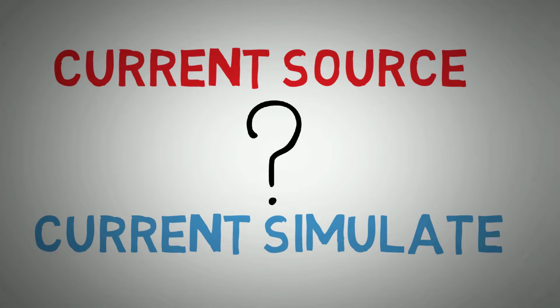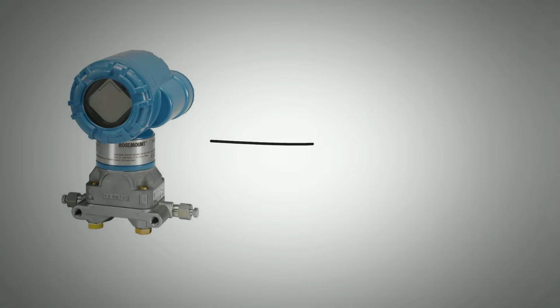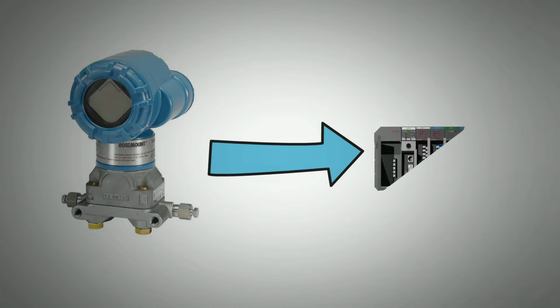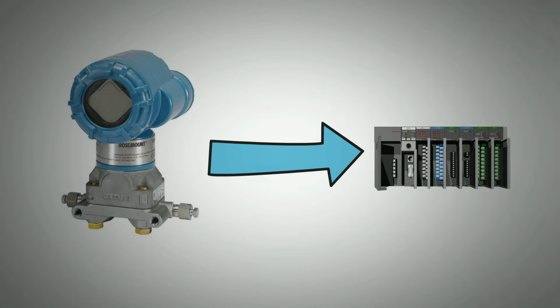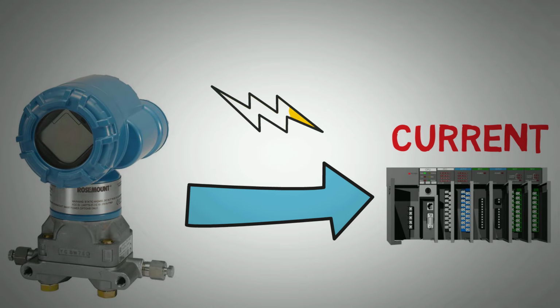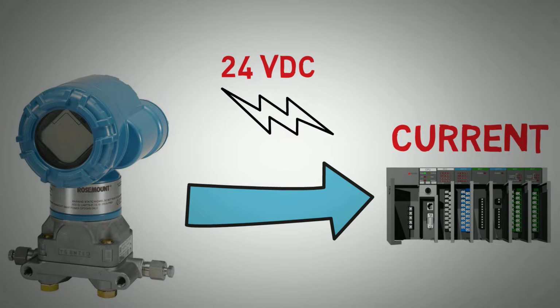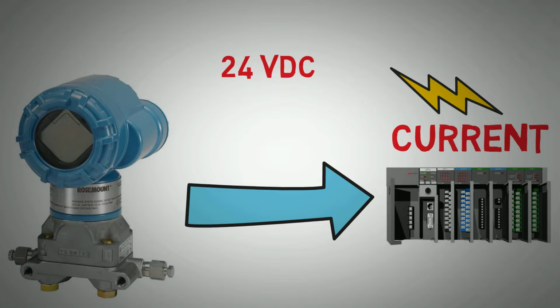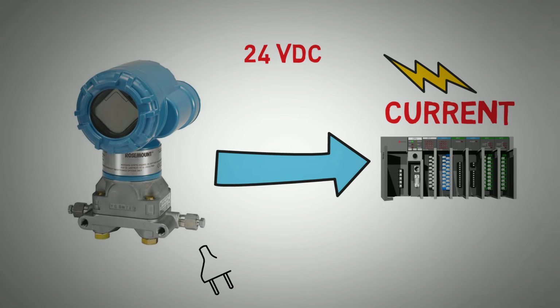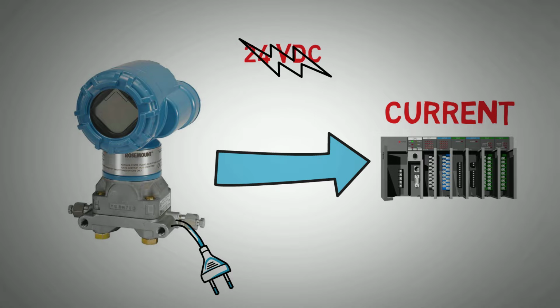Quickly, before we move on to the steps on how to use the Fluke 789, we should discuss the difference between sourcing and simulate modes. Transmitters and other sensors that give 4 to 20 milliamp signals are connected to a PLC or other input device that reads the current within the loop. These current loops are usually 24 volt DC powered. These instrumentation loops can either have the 24 volts powered from the input card, or the transmitter is externally powered and it provides the 24 volts for the loop power.